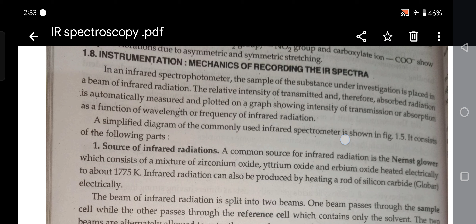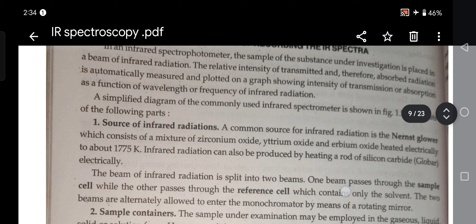Instrumentation and mechanics of recording the IR spectra. In an infrared spectrophotometer, the sample of substance under investigation is placed in a beam of infrared radiation. The relative intensity of transmitted and therefore absorbed radiation is automatically measured and plotted on a graph showing intensity of transmission or absorption as a function of wavelength or frequency of infrared radiation.